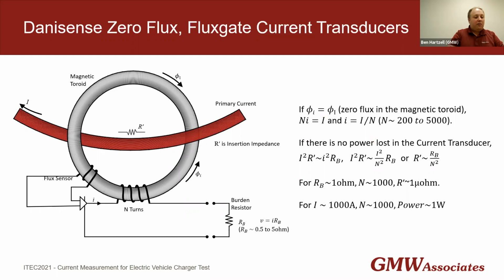Following the equations here on the right, if there is zero flux in the magnetic toroid, which is what we expect, the secondary current is equal to the primary current divided by the number of turns, again, typically 200 to 5,000. If there is no current lost in the current transducer, so no current lost in the core because of very good magnetic core materials, and no power lost to the secondary compensation coil, then the insertion impedance should be roughly equal to the burden resistance over the number of turns squared.